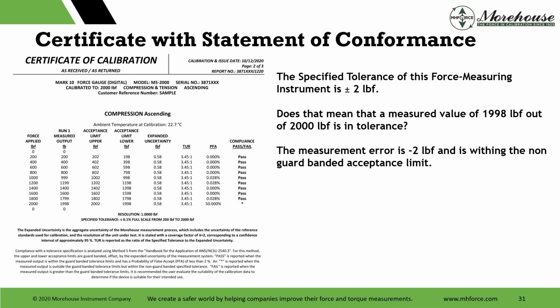Here's a case right here. You start seeing pass, pass, pass, and then you see an asterisk at the bottom. The instrument has a specified tolerance of plus or minus 2 pounds of force. Does that mean that a measured value at 1,998 pounds of force out of 2,000 is in tolerance? The measurement error or bias is negative 2 pounds and is within a non-guard banded tolerance or acceptance limit.